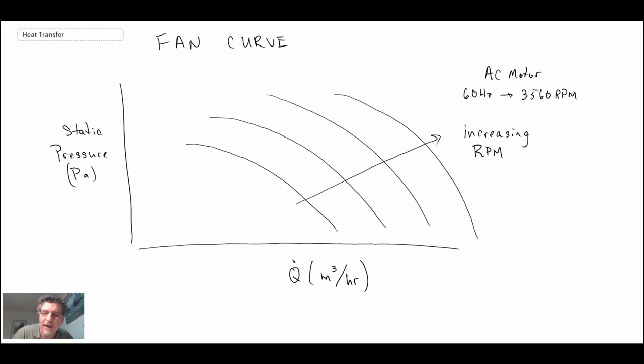So you wouldn't want these fans spinning at that high of a speed or rotational rate. So what you would do is you would either have a pulley system to reduce the rotational rate or you would have a gearbox that would reduce the rotational rate. If you have 50 hertz power, other parts of the world have that and there we would get 3000 rpm would be what would be coming off of the motor, the electric motor in this case. So anyways, the increasing rpm is going in that direction, depends where you are and what it might be. And using belts or a gearbox you can change the rpm that you're at.